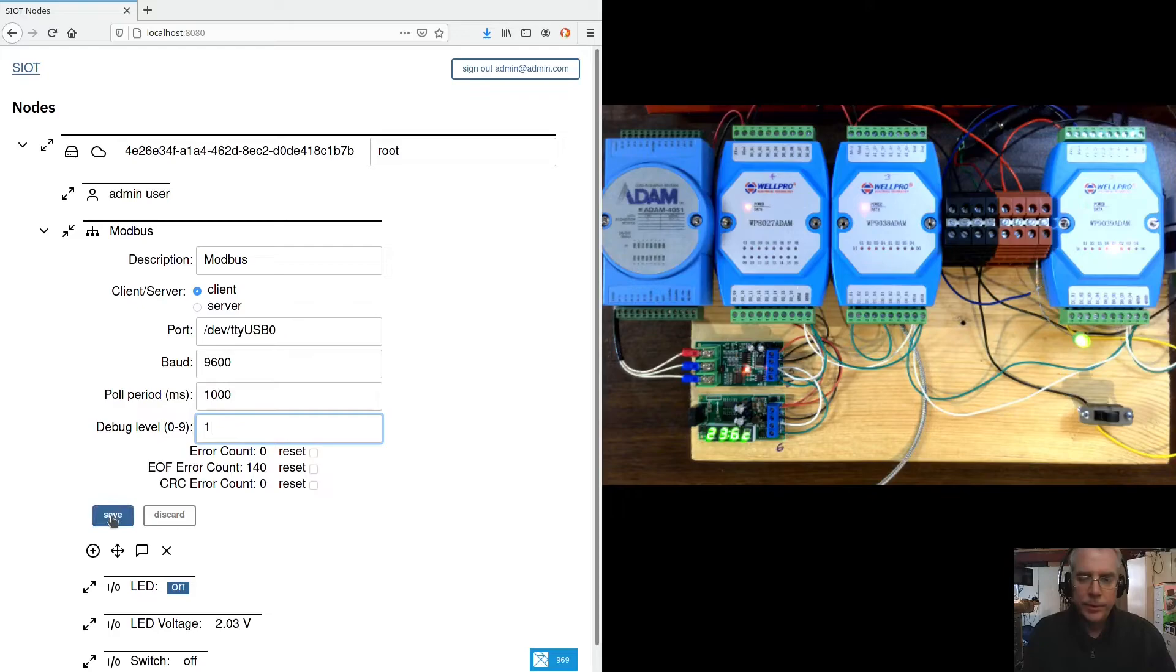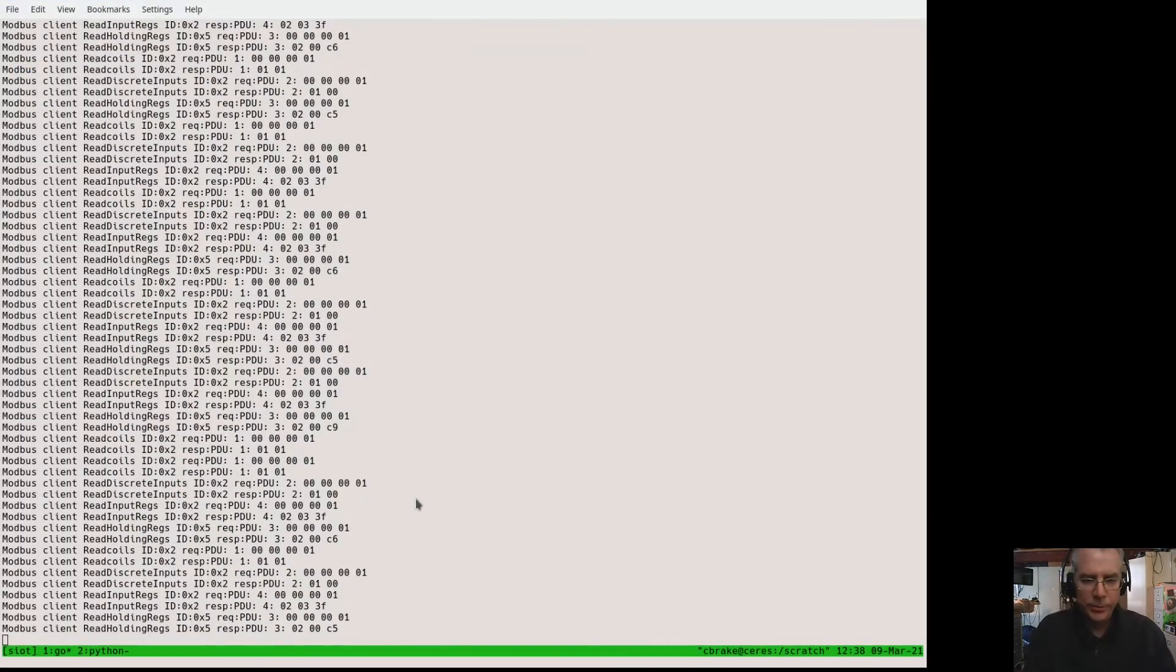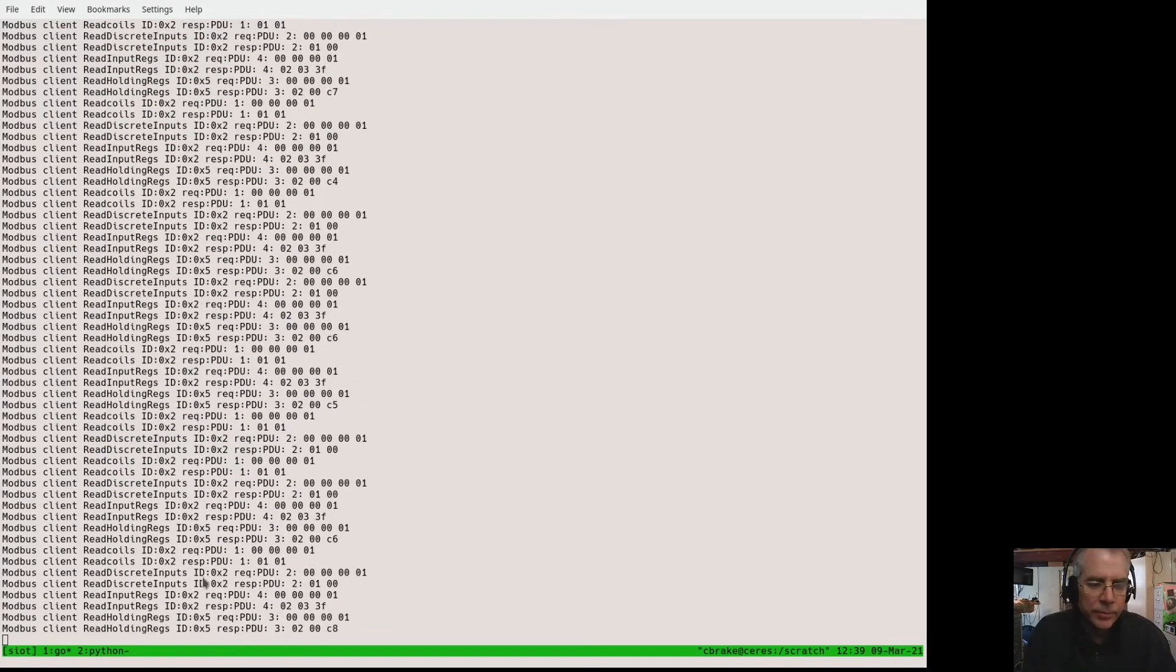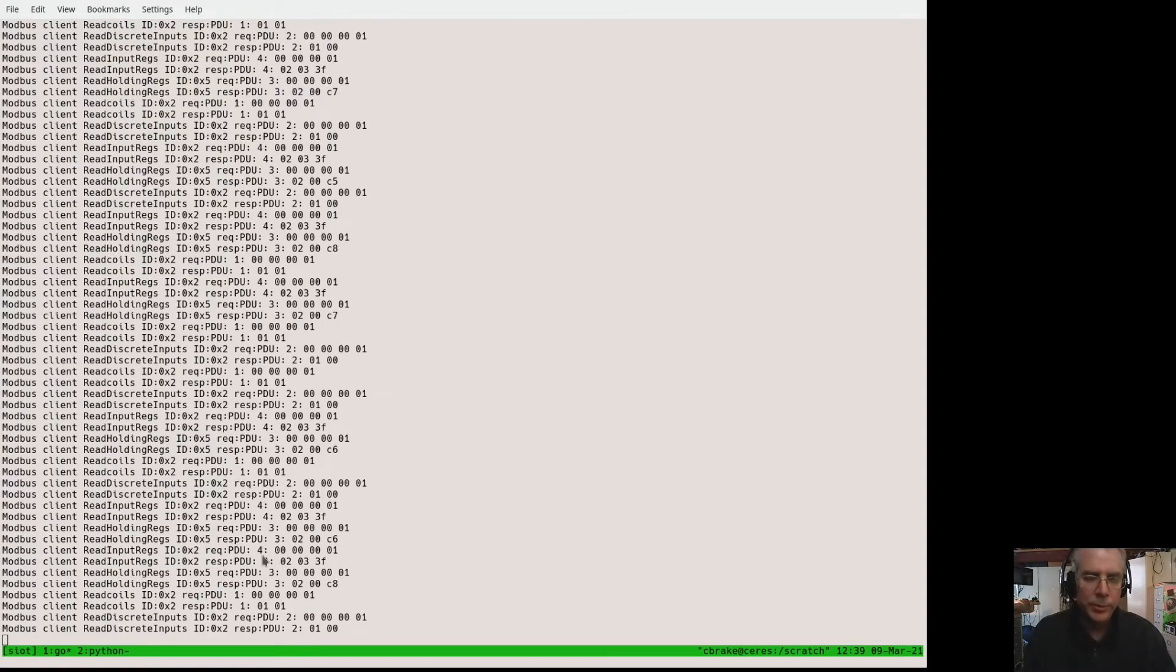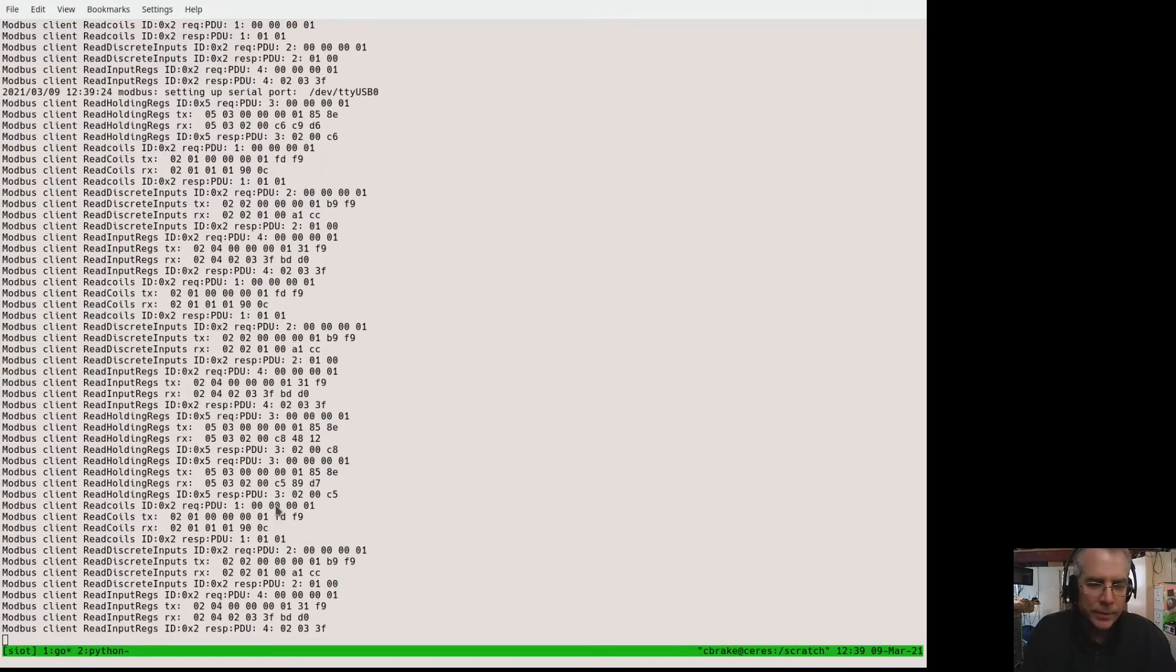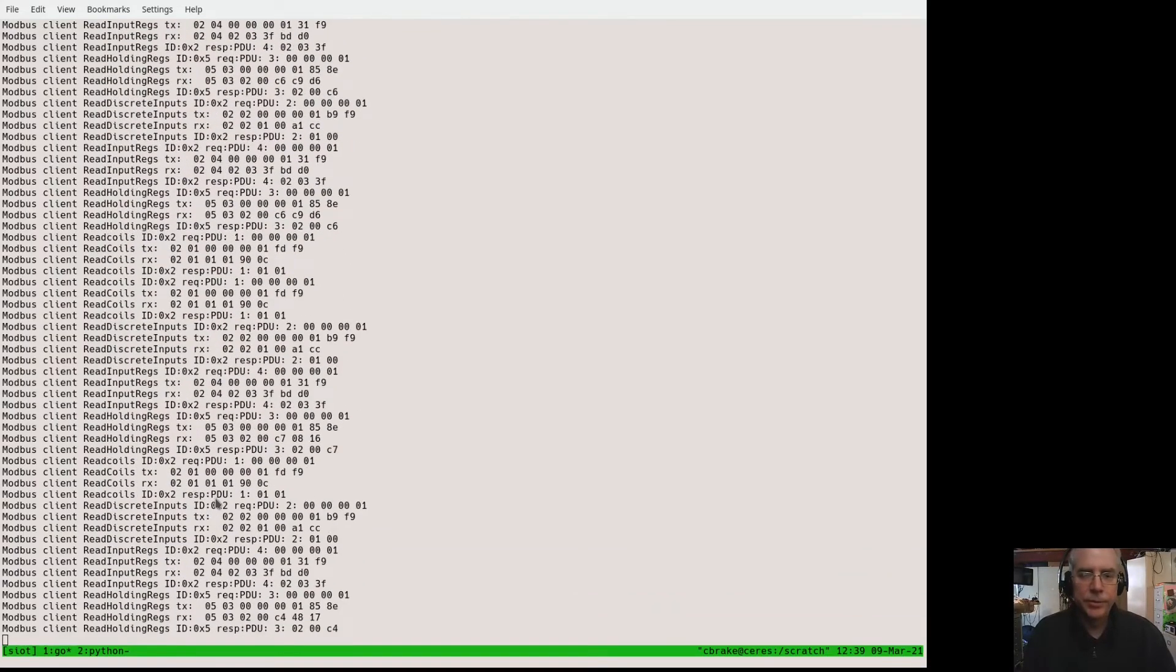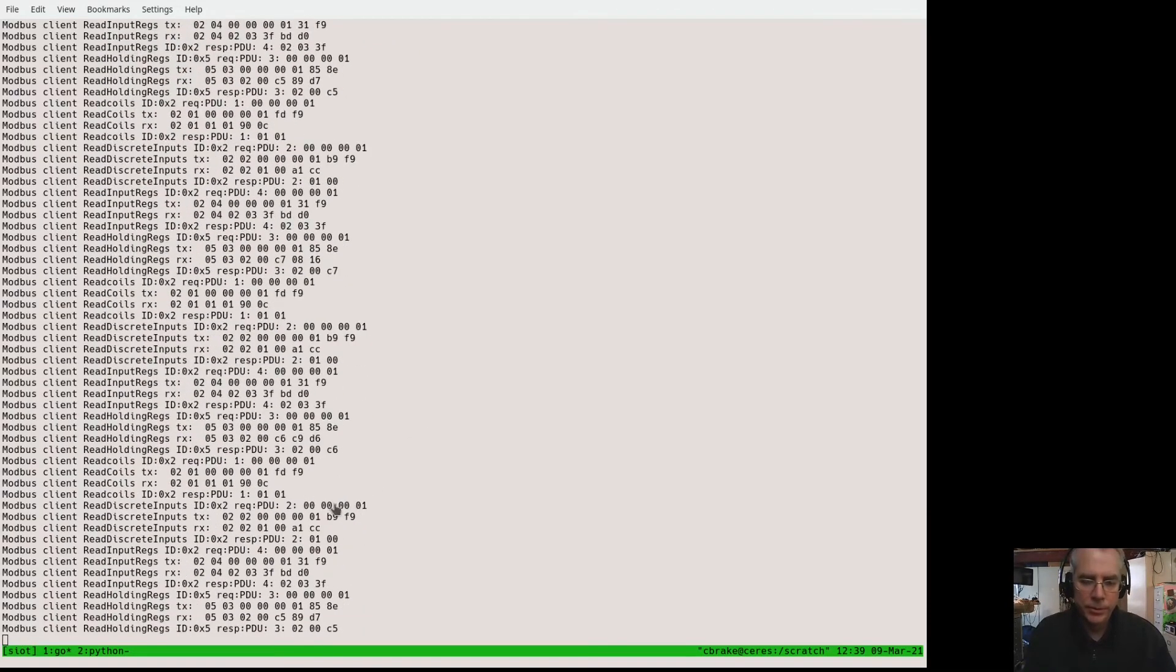We can increase the debug level. And if we do that, it'll actually show us the Modbus levels or the Modbus data that's going across the bus. So you can see it's showing the actual Modbus operations and the data that's being transferred to and from each device. If we take the debug level up to nine, now it actually shows us, in addition to all that, the raw data that's on the bus. So typically you can use this if you're trying to debug a problem or learn how to read a new device. So I'll turn that back off.